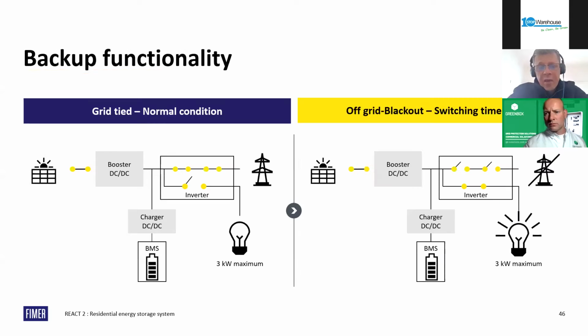The backup functionality, there's a 3 kilowatt backup circuit on the React 2. So the picture on the left, under normal conditions, when there's a grid available, there is no output on the 3 kilowatt maximum backup circuit. Grid shuts off. There is a switching time. It's not a UPS. It doesn't happen instantaneously. It's about a 2-second changeover, and then the backup will arrive at the backup circuit. You can wire either an essential service or a designated circuit inside the inverter. I have seen contractors mount a couple of contactors in the main switchboard to switch between the grid and this backup circuit as well.